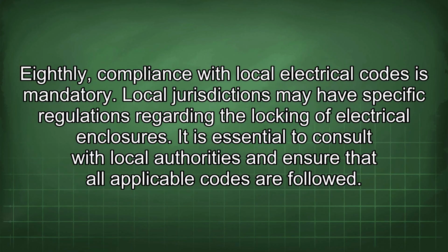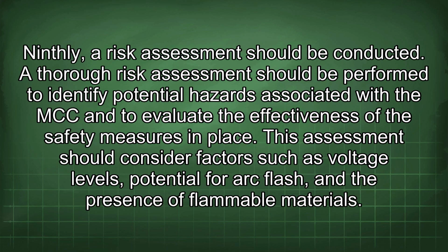Eighthly, compliance with local electrical codes is mandatory. Local jurisdictions may have specific regulations regarding the locking of electrical enclosures. It is essential to consult with local authorities and ensure that all applicable codes are followed. Ninthly, a risk assessment should be conducted. A thorough risk assessment should be performed to identify potential hazards associated with the MCC and to evaluate the effectiveness of the safety measures in place.